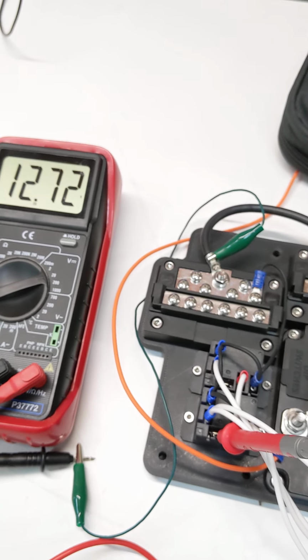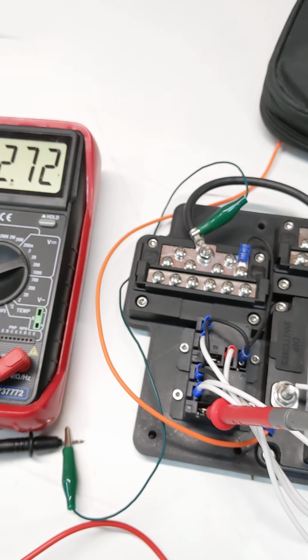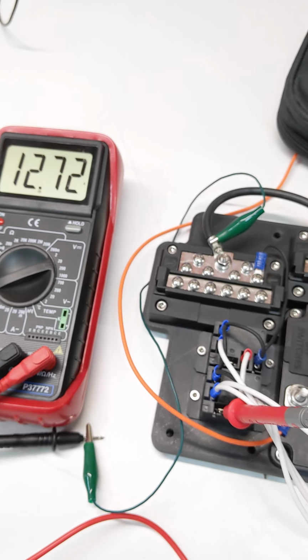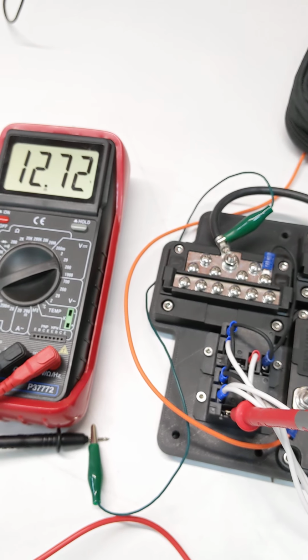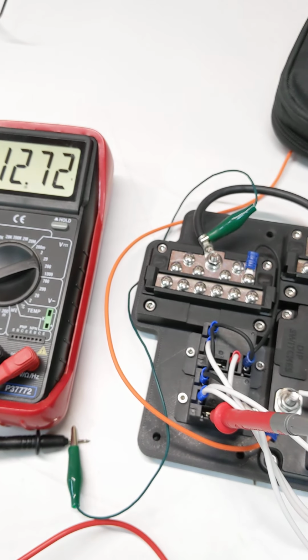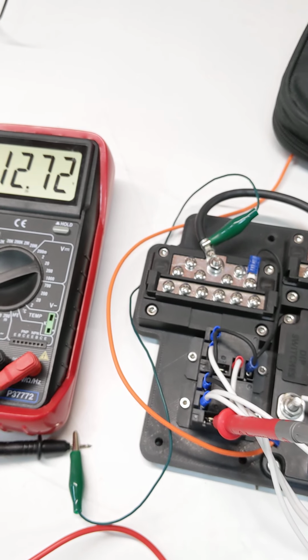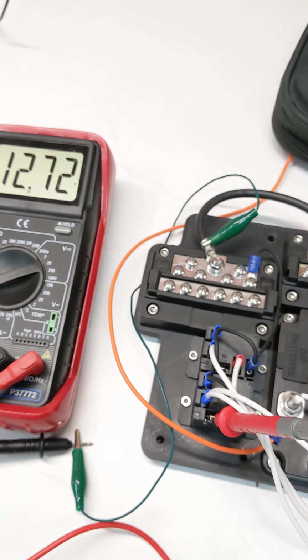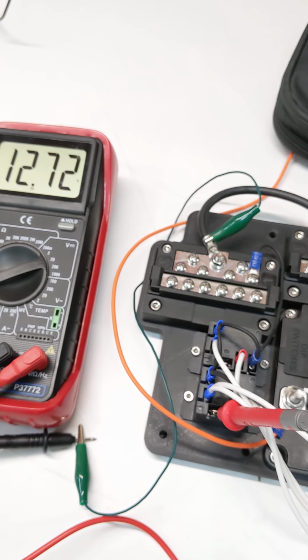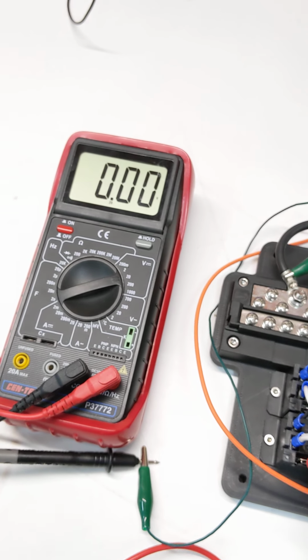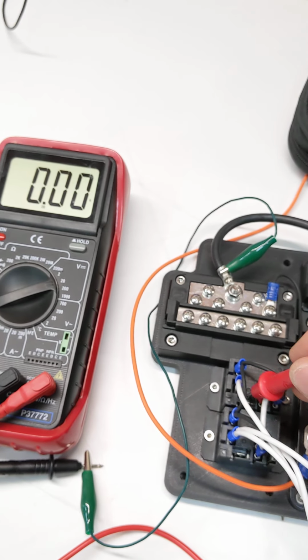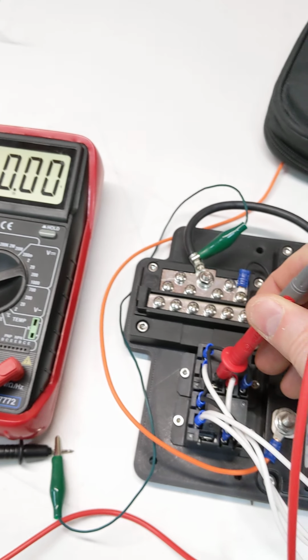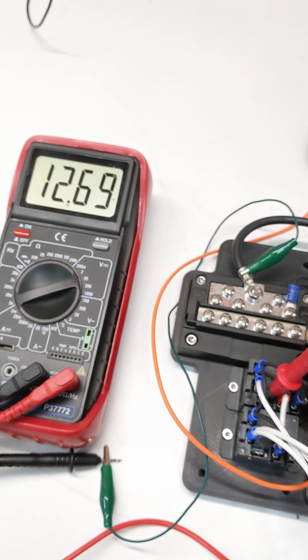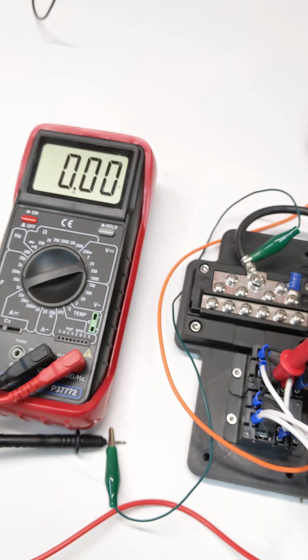After the push button is released, this wire that I'm holding, once I release this wire, that'll indicate the push button has been released. Immediately the power will go away from the unlock door, and then 9 seconds later we're going to monitor the output of the second Form C relay, and that relay will turn on for 1 second, only 9 seconds later. So let's go ahead and remove this connection. That has been removed. Now we're going to move our probe here to the other relay, and at the 9 seconds you'll see the voltage turn up and then off 1 second later. That would indicate the relock of the rear door.